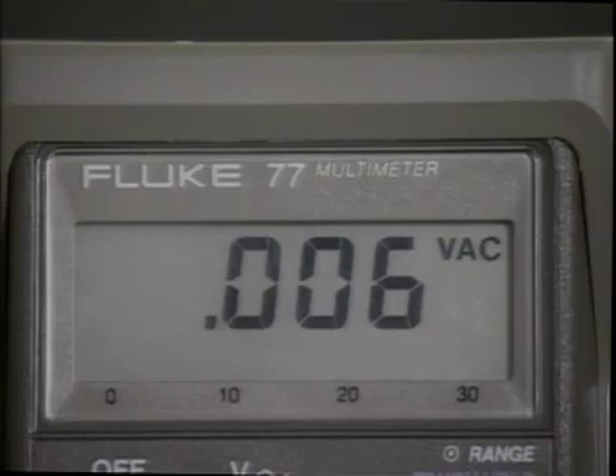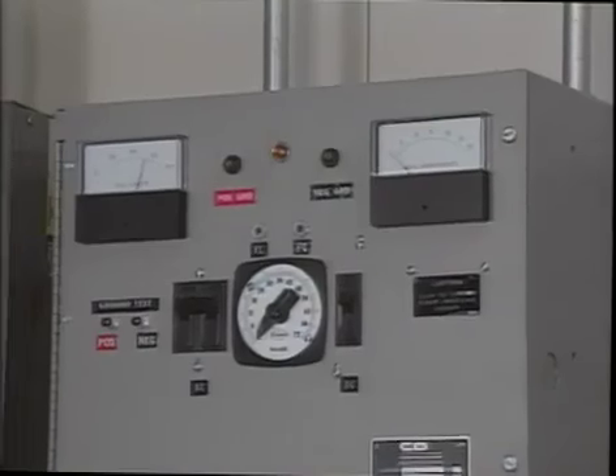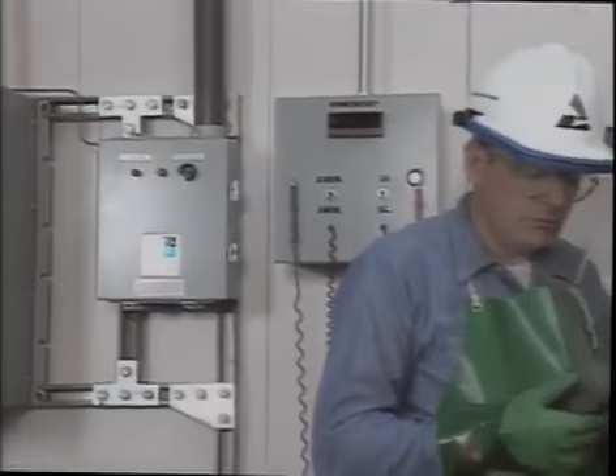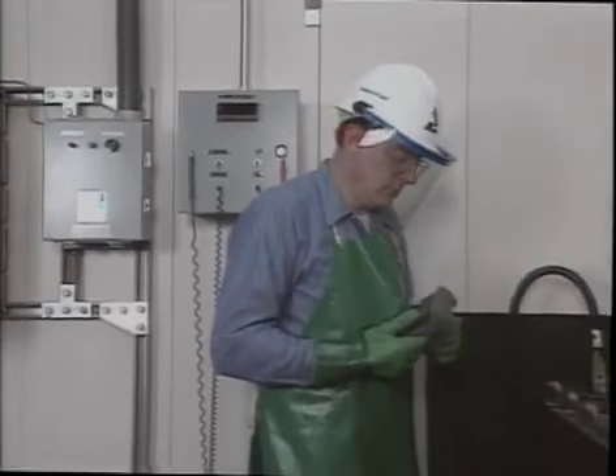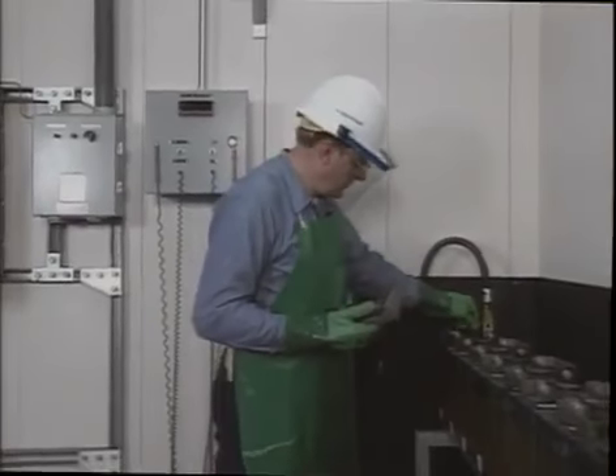If a charger is going bad, there will be a large AC voltage output from the charger, and the charger would need to be replaced. The float and equalize voltage settings should also be checked periodically. This can be done using a precision voltmeter or multimeter that's switched to a DC voltage setting.